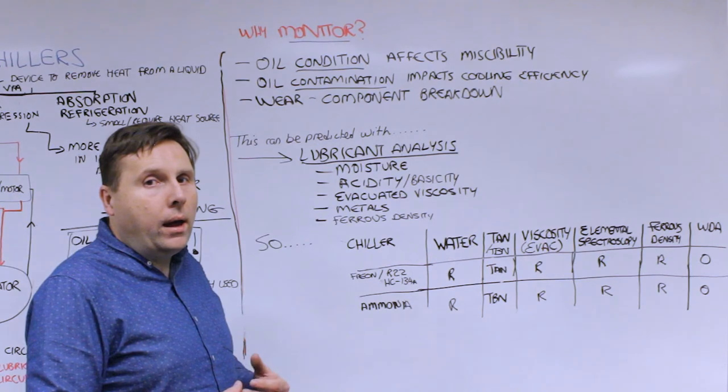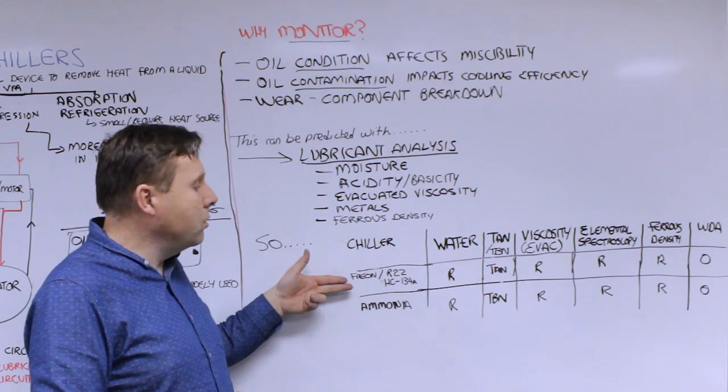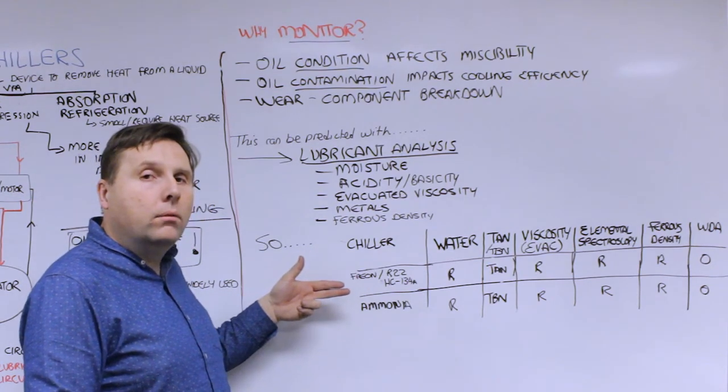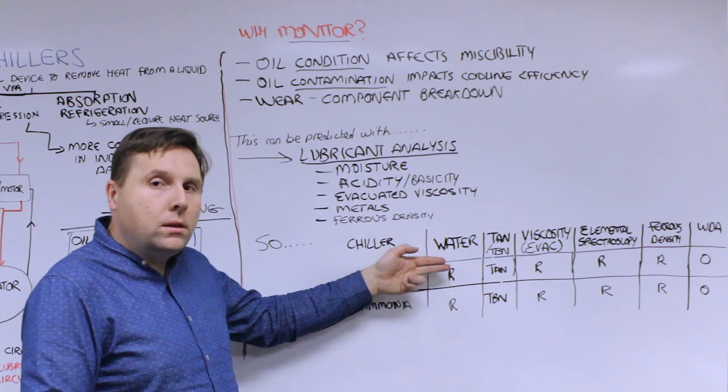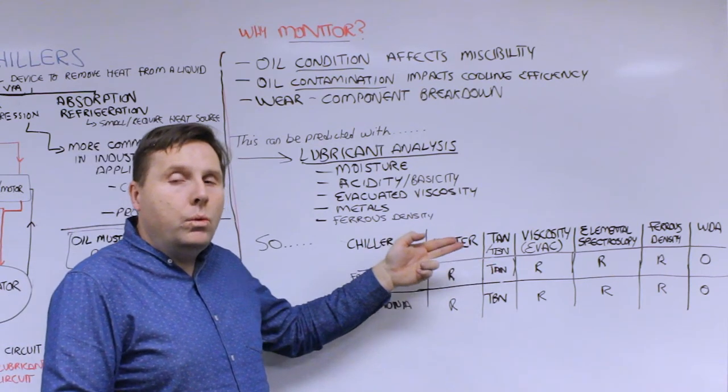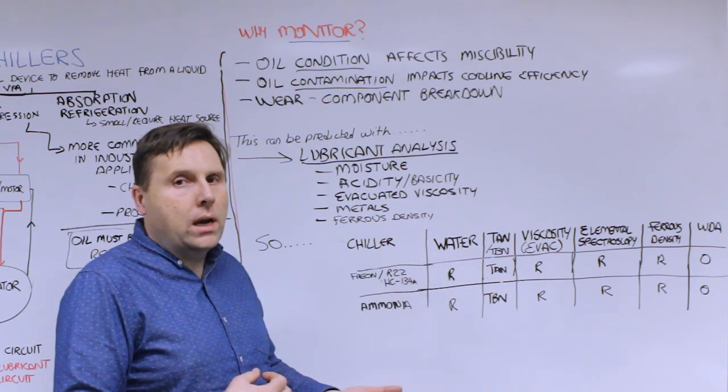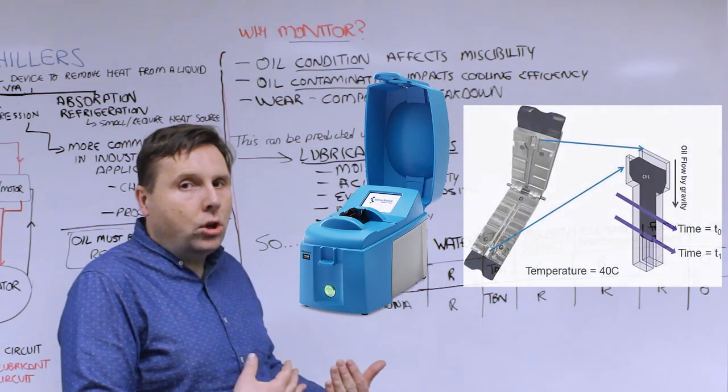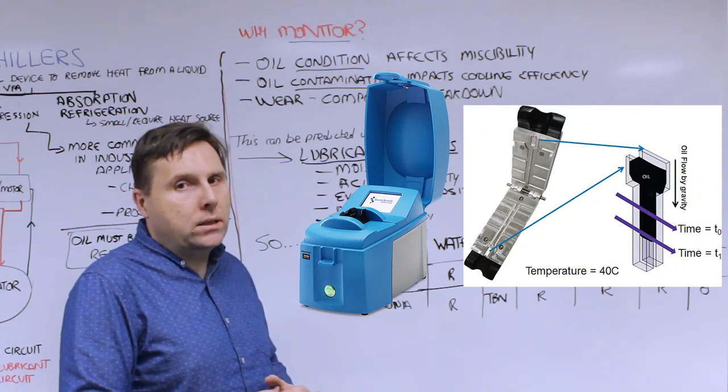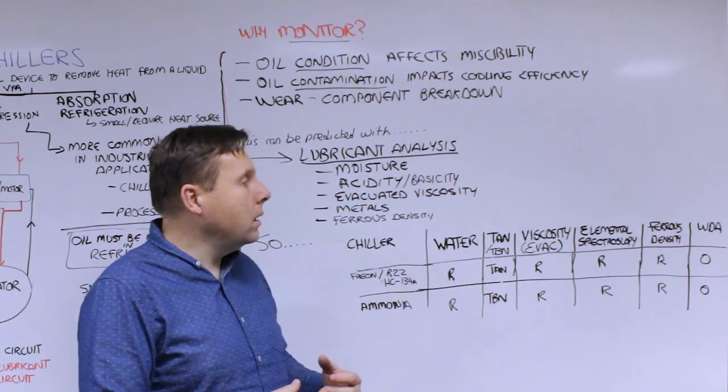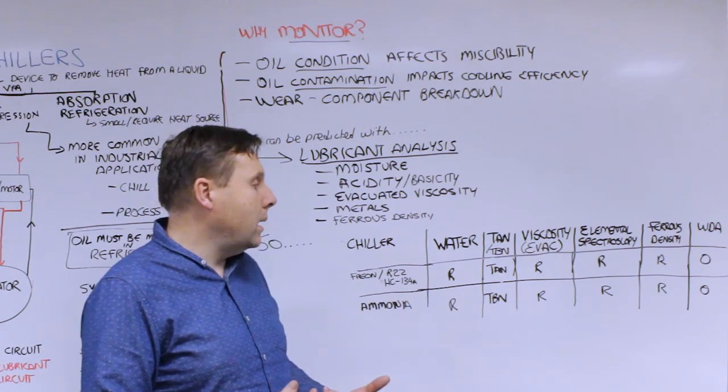When we recommend running oil analysis tests for these systems: if you have a freon, R22, or HC134 chlorinated based refrigerant, we recommend you run water analysis, total acid number to look at acidity, viscosity—when we say evacuated viscosity you want to remove that refrigerant before you run the viscosity. If you use a MiniVis system with the Hele-Shaw cell, you do not have to remove it; you can introduce the sample directly and it out-gases as it's running. Include elemental spectroscopy for wear metals, ferrous density for large debris, and wear debris analysis as an option. For ammonia based systems, everything's the exact same except for acidity—we're worried about basicity.